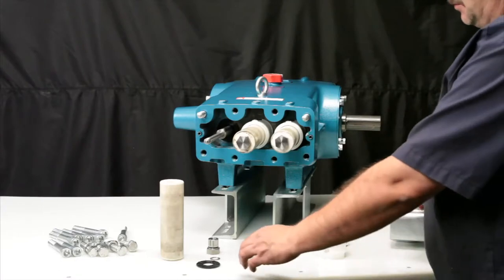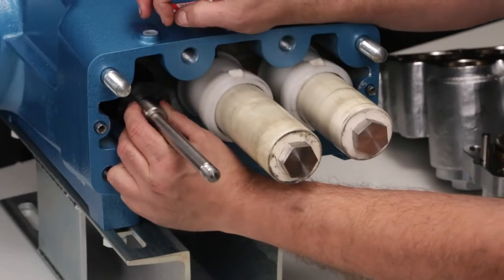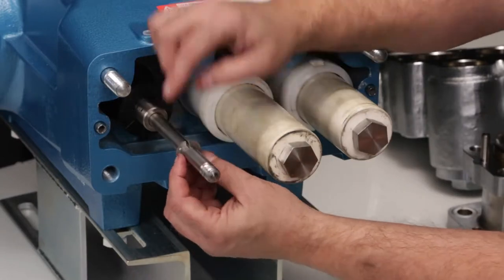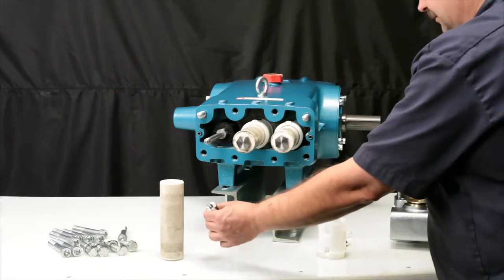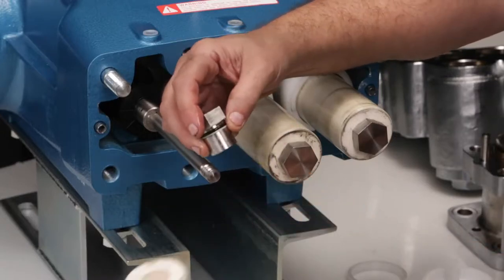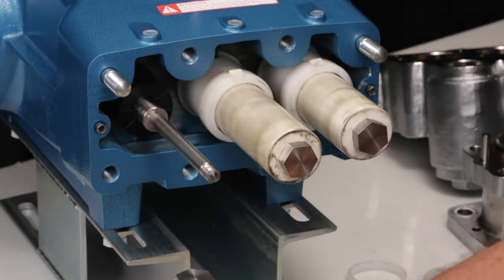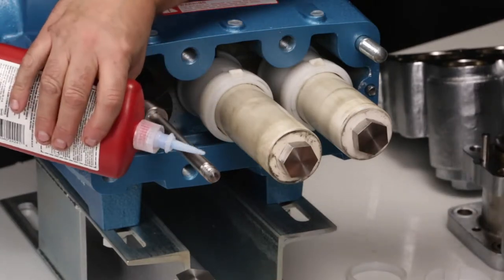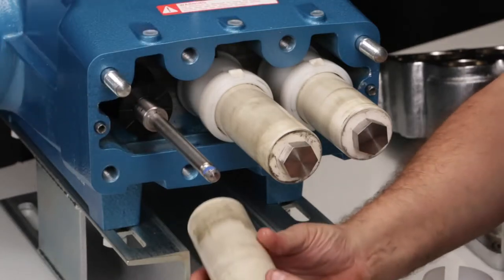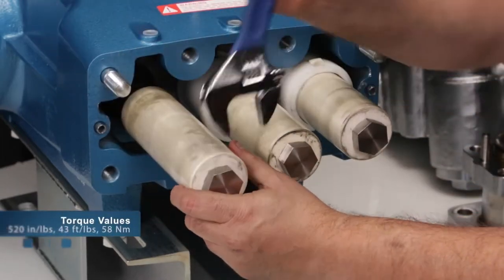To begin reassembly, install the new O-ring followed by the backup ring onto the plunger retainer. Next, install the rubber barrier slinger followed by the keyhole washer — the slot opening can face any direction. Lubricate the O-ring and backup ring on the plunger retainer. Install the plunger retainer assembly through the ceramic plunger — this can only be installed in one direction. Before installing, apply liquid thread sealant to the threads of the plunger rod. Hand thread the plunger retainer assembly onto the plunger rod, tighten using a wrench, and torque to specification.